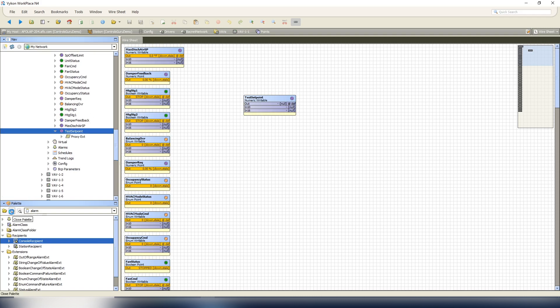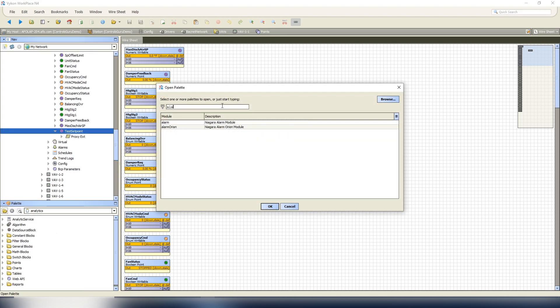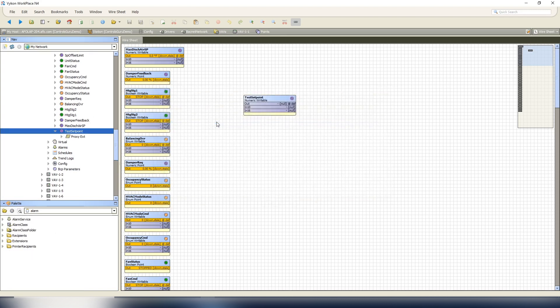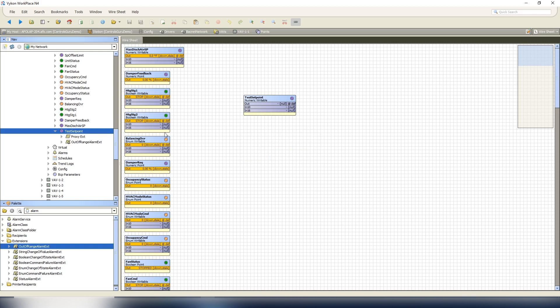Open up our alarm palette. If you don't know how to do that, if it's not already open, just hit this open here, type in alarm, there's your Niagara alarm module, your extensions. Now for a set point we're going to grab the out-of-range alarm extension and drop it onto our test set point.